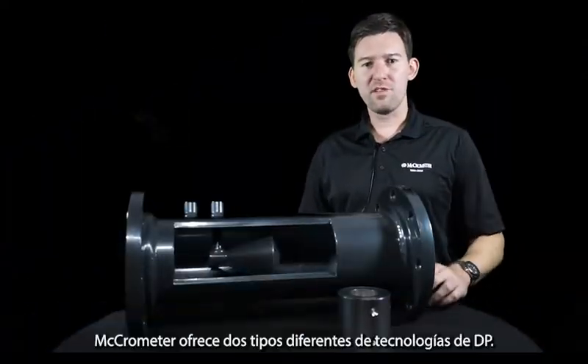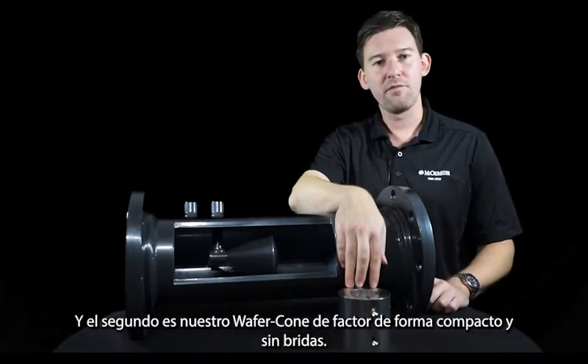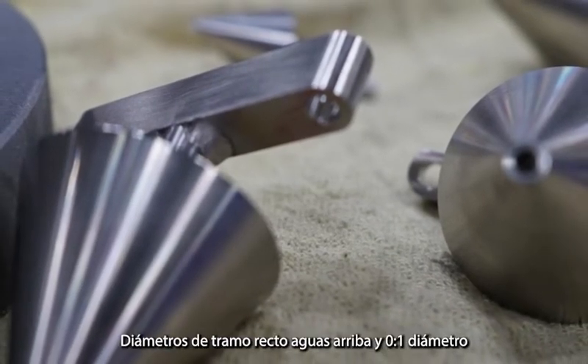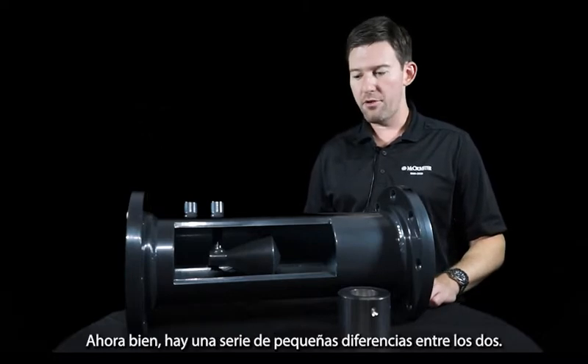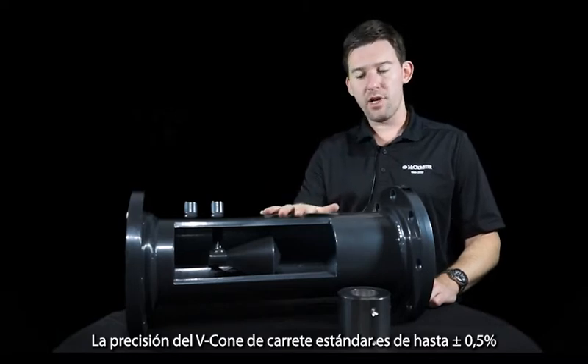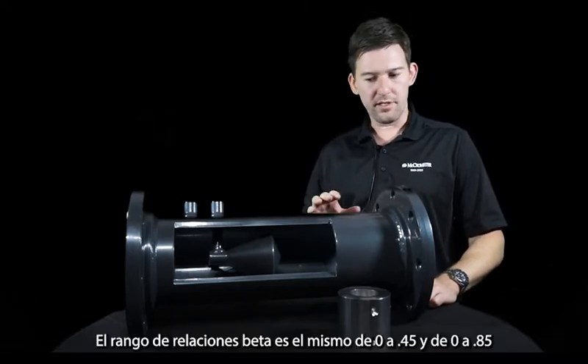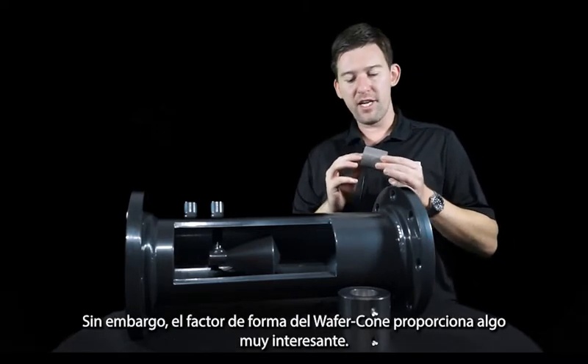McCrometer offers two different types of DP technologies. The first is our standard spooled V-cone, and the second is our compact, flange-less form factor wafer cone. There are a number of similarities — besides the shared technology, both have the same straight run requirements: zero to three diameter upstream and zero to one diameter downstream. There are also slight differences: the accuracy of the standard spooled V-cone is up to half a percent, while the wafer cone is up to plus or minus one percent. The range of beta ratios is the same, from 0.45 to 0.85. However, the form factor of the wafer cone provides something very interesting.